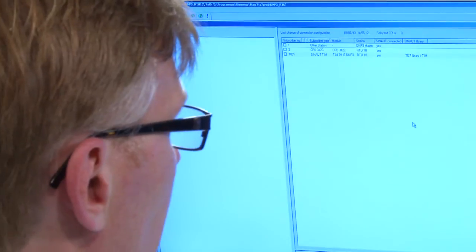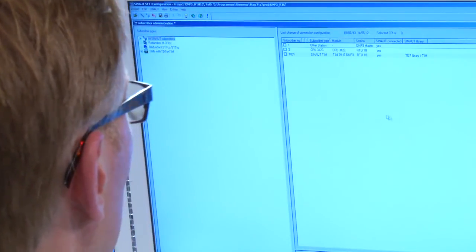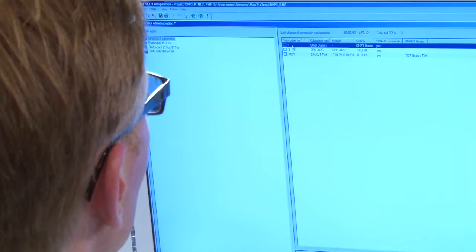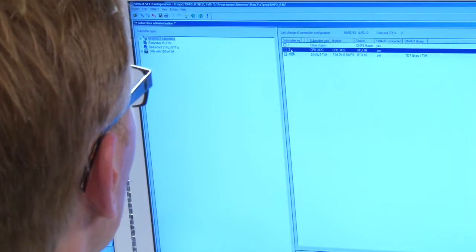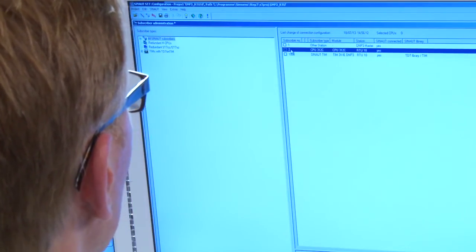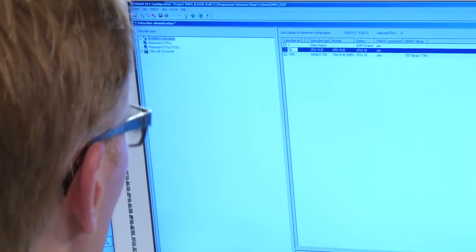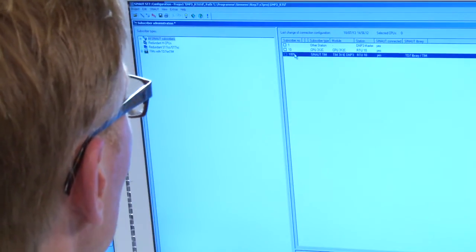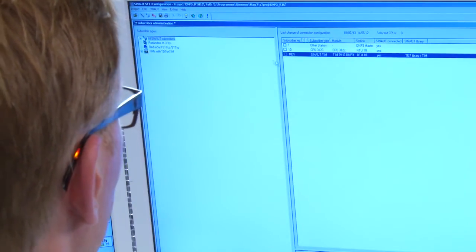A DNP3 address is the individual address that a communications partner of the telecontrol project uses to exchange its process information, for example, process values such as pressure, temperature, alarms or status information. I assign the addresses as specified in our example. The master is assigned DNP3 address 1 and the station DNP3 address 10. The default address should be kept for the TIM.